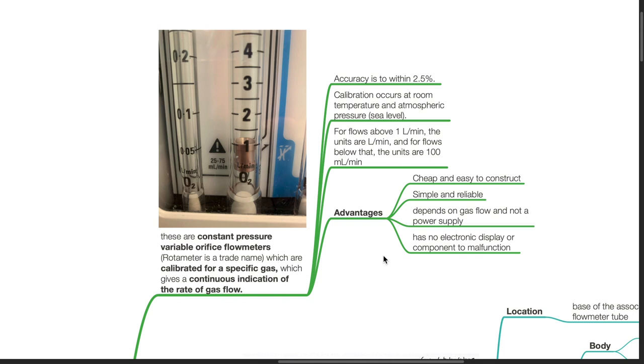Rotameter is a trade name. They are accurate to within 2.5%. Calibration occurs at room temperature and atmospheric pressure at sea level. For flows above 1 liter per minute, the units are liters per minute and for flows below that, the units are 100 mls per minute.